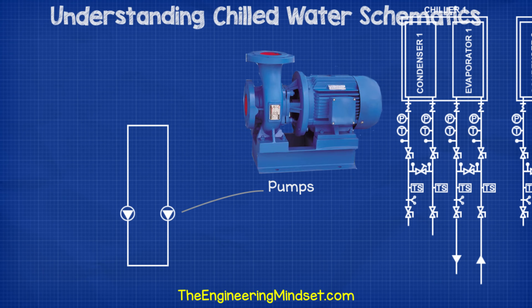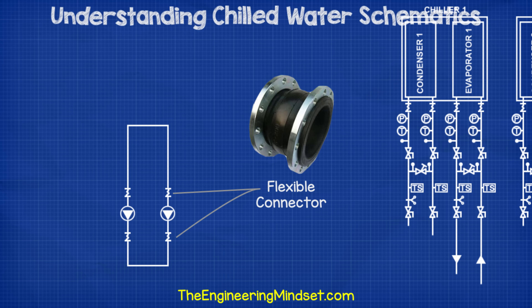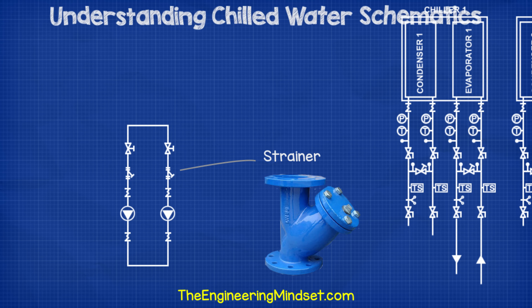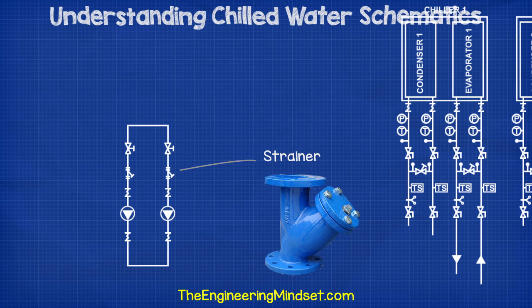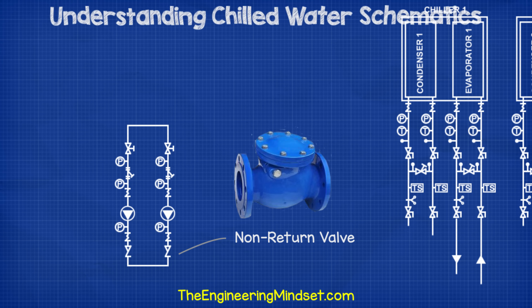Next, we'll need some pumps to push the water through the chiller and around the building. For this, we'll usually have two or more pumps in parallel, typically running in duty and standby — the triangle points in the direction of flow. Then we'll need some flexible connectors as the pumps will cause vibrations. Then we'll want some isolating valves so that we can cut one or all of the pumps off for maintenance. Then we'll have some strainers which capture the particles and dirt in the water and prevent them from entering the pump and causing damage — some pump setups don't use this, and some will use just one large strainer elsewhere in the system. Then we'll have some pressure gauges to allow manual readings. Then we'll have a non-return valve which prevents the pressure in the pipework from forcing the pump to rotate backwards when it's turned off.